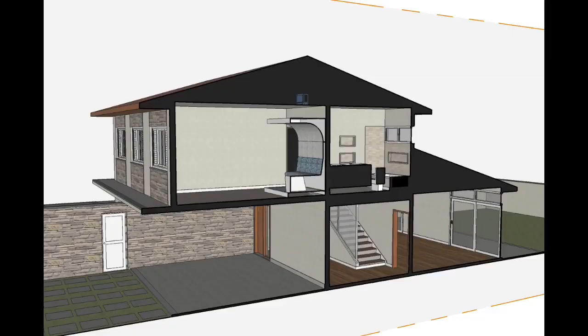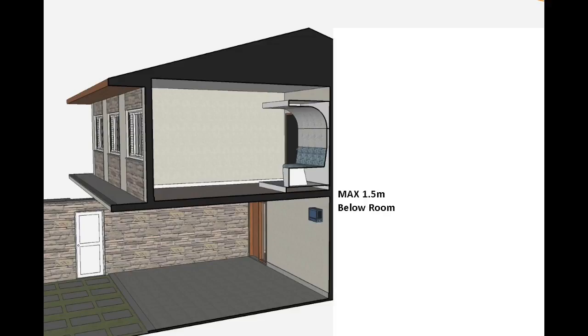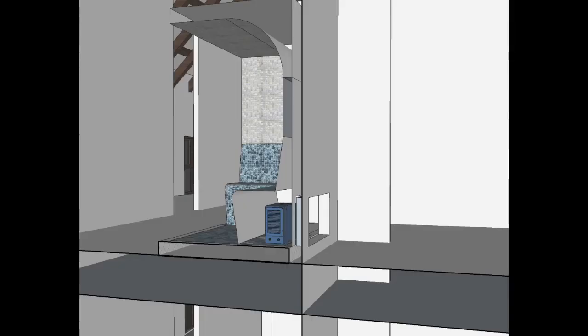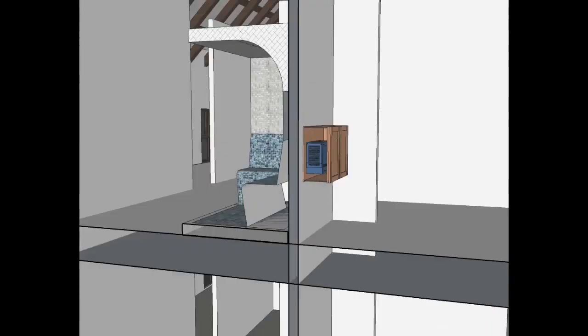Location. The steam generator can be installed in a number of locations. For example, in the loft, or in a room above the steam room, below the steam room but no lower than 1.5 meters underneath the floor of the steam room, under the benches of the steam room but only if the access is from outside of the steam room, or in an enclosed cupboard adjacent to the room.